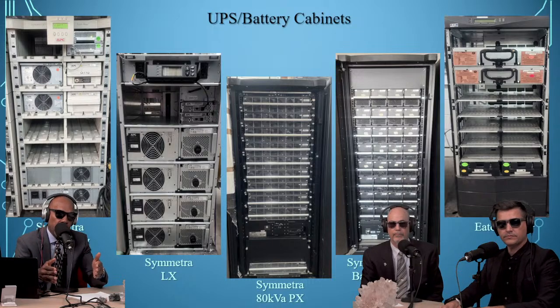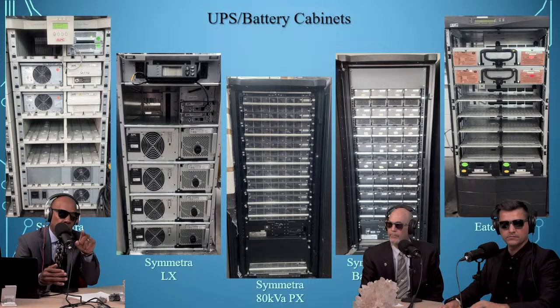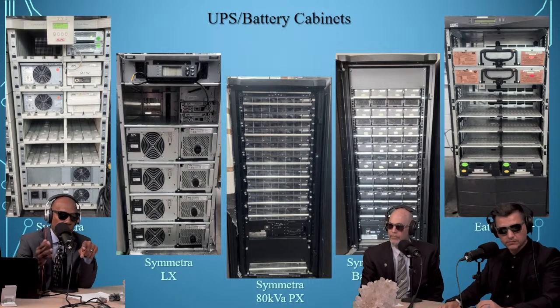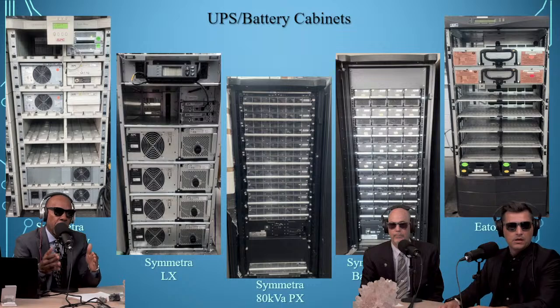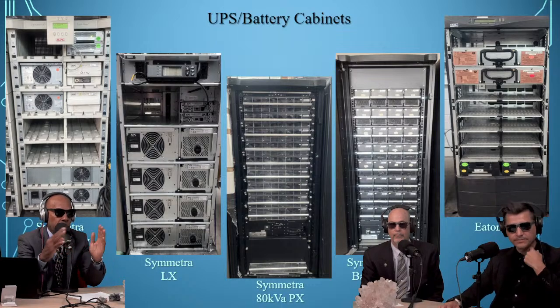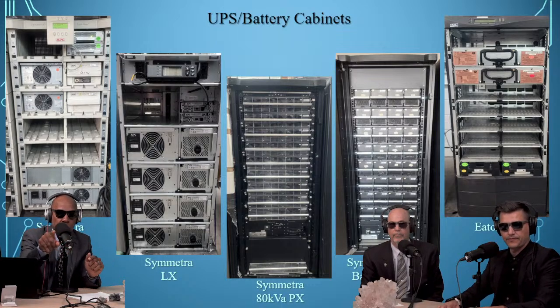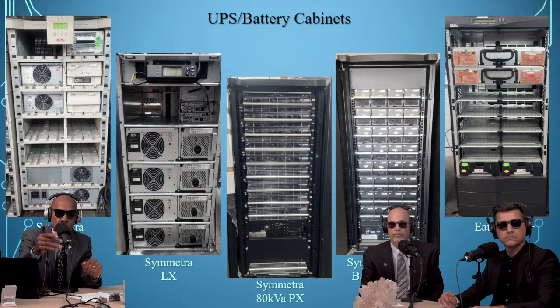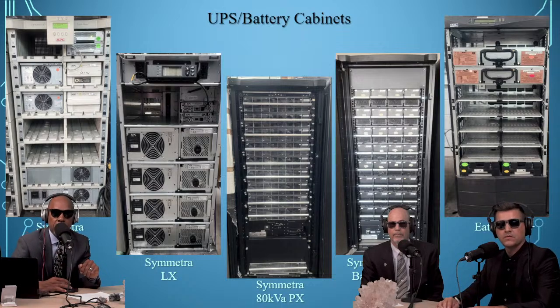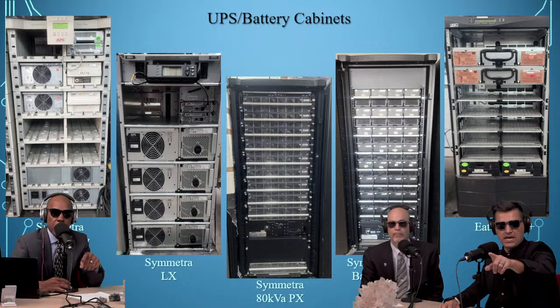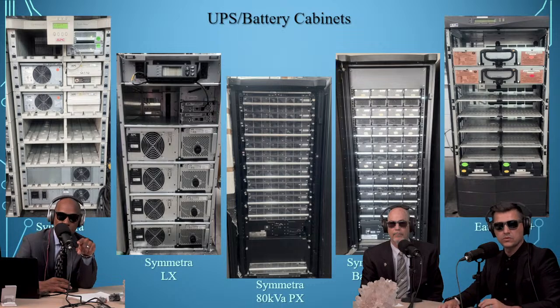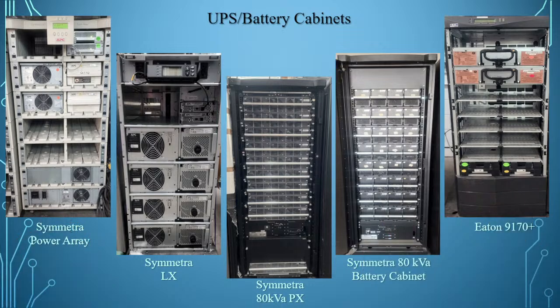Go back to the second unit from the left. You see the 4 battery modules on the right? Those are internal batteries because they're internal to the frame. If you look at the PX80 with all the power modules fully populated, you have an extended battery cabinet, 32 modules, 8 strings. That's the 4th one over, and there's 8 power modules, 8 strings.